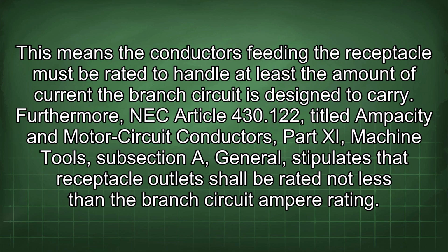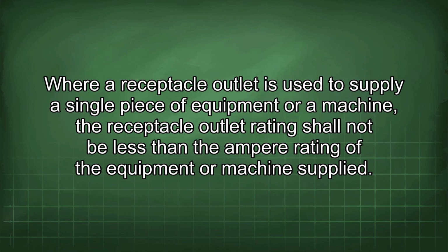Furthermore, NEC Article 430.122, titled Ampacity and Motor Circuit Conductors, Part Roman 11, Machine Tools, subsection A, General, stipulates that receptacle outlets shall be rated not less than the branch circuit ampere rating. Where a receptacle outlet is used to supply a single piece of equipment or a machine, the receptacle outlet rating shall not be less than the ampere rating of the equipment or machine supplied.